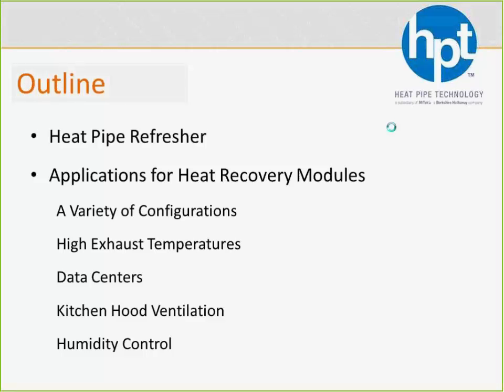I always like to start off with a quick refresher on what a heat pipe is and how it works, or more specifically how our heat pipe works, because the HPT heat pipe is a little bit different from the others that are out there. But the main focus of today's webinar is on the various applications in which the heat recovery modules can be used, from the various configurations that we can work with, as well as specific applications like high temperatures, data centers, using heat recovery heat pipes in kitchen hood ventilation, which will actually meet an ASHRAE standard. And then what's interesting, if you're familiar with the wraparound heat pipe and that it's used for dehumidification, there's the heat recovery heat pipe for dehumidification. So I'm going to cover that as well.